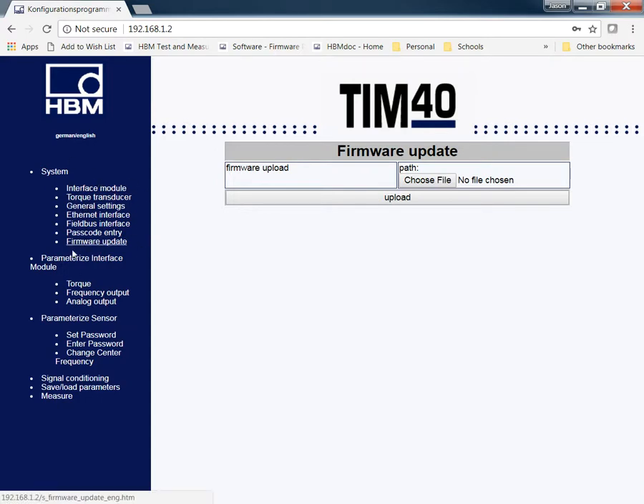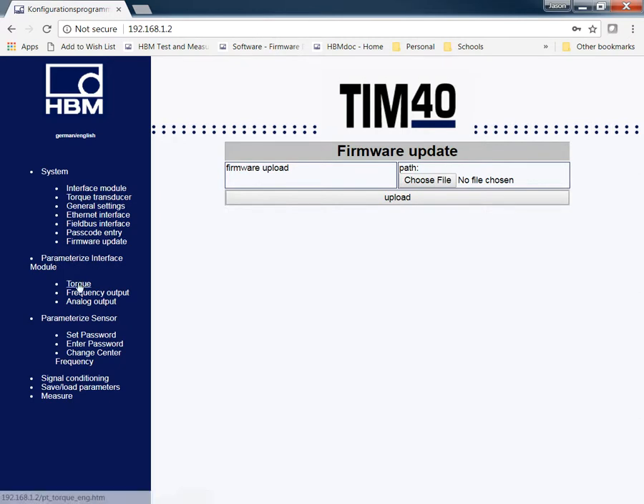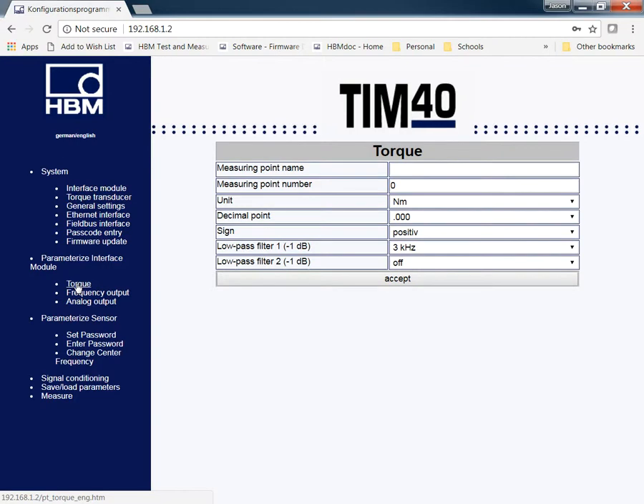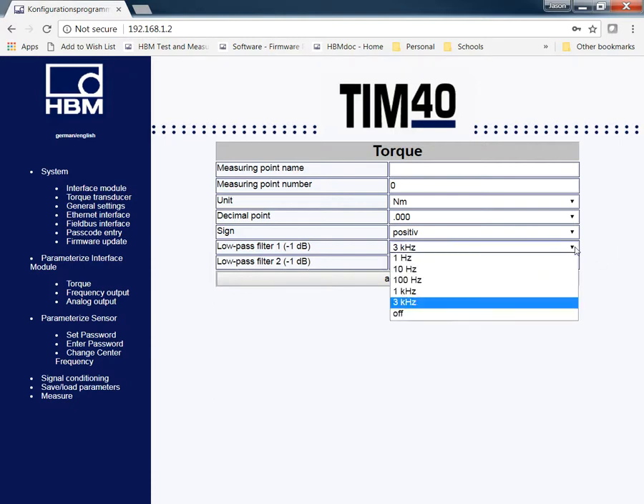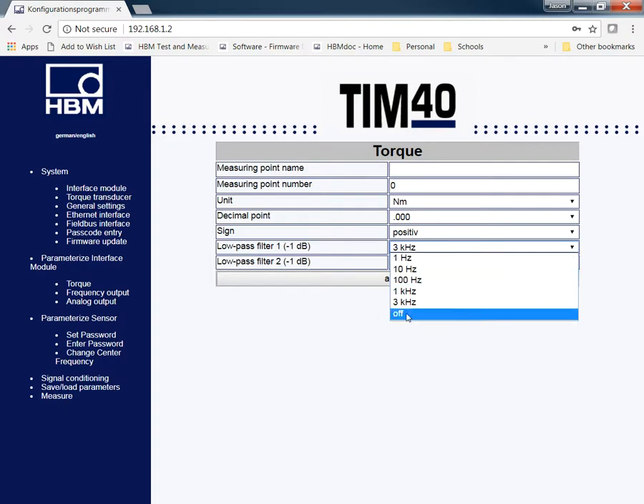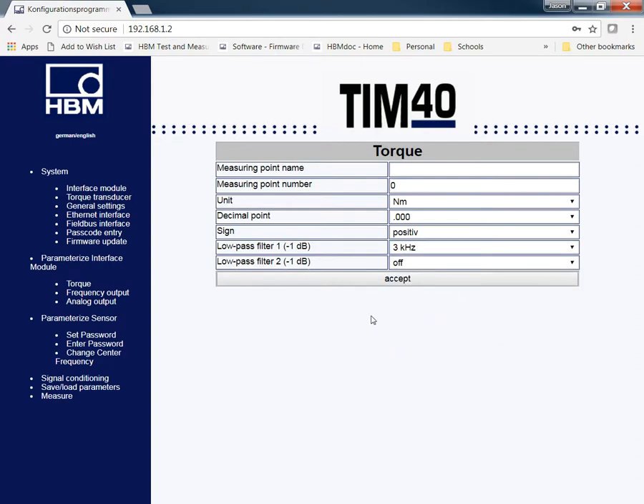The main tab is a parameterized interface that I wanted to go into. From the torque side, this is when you can go through and put in different decimal points that you want, your sign, positive and negative. Basically, what that is, if you look at the rotor, put the rotor on the desk with the HBM logo facing up, clockwise is positive, counterclockwise is negative. There's a couple different options for low-pass 1 and low-pass 2, 1 Hz to 3K, or you can simply just shut this one off if you want to do the exact values coming right off of your system that's being unfiltered.